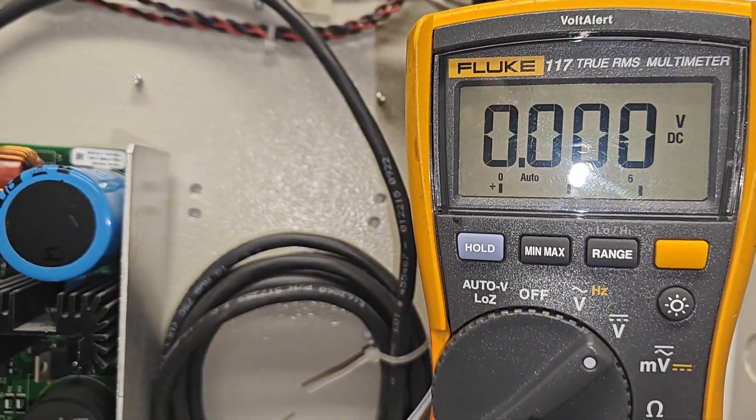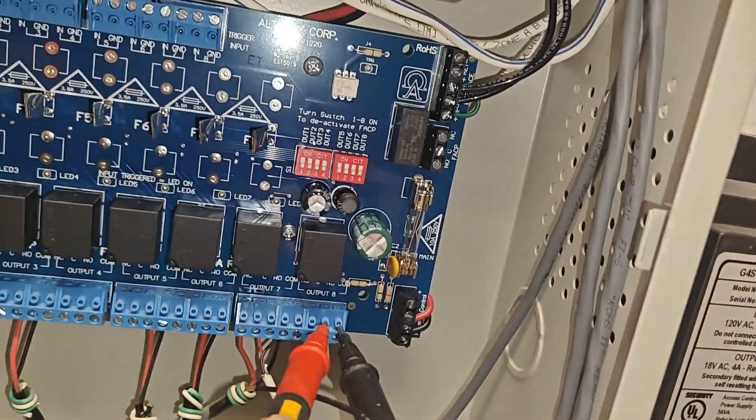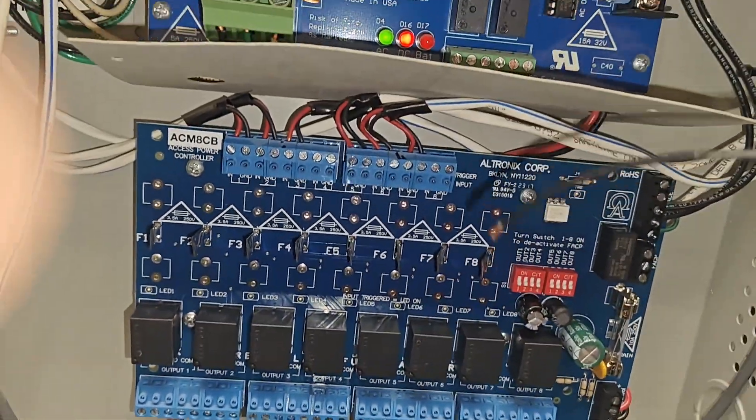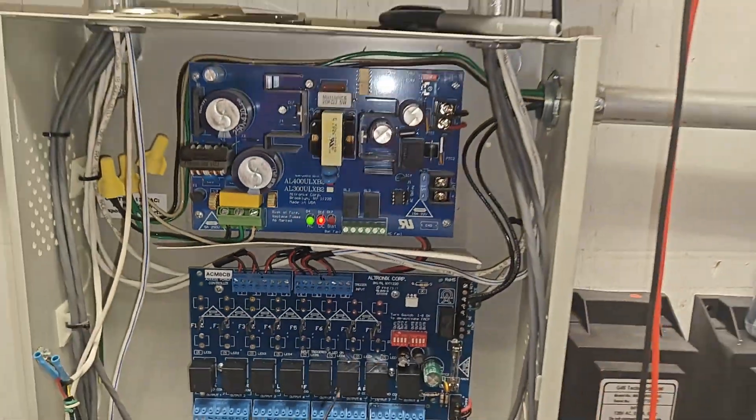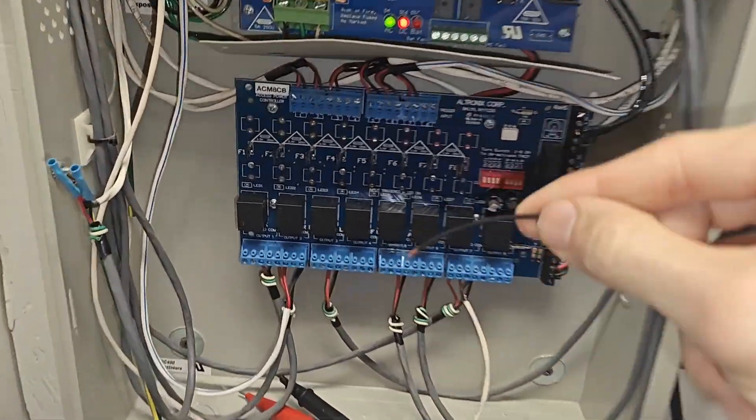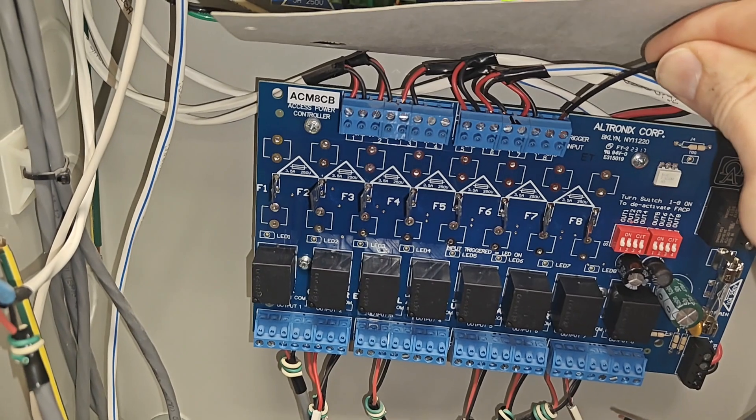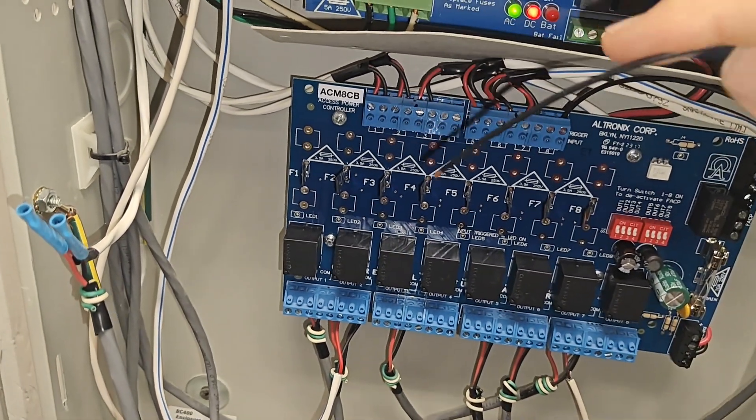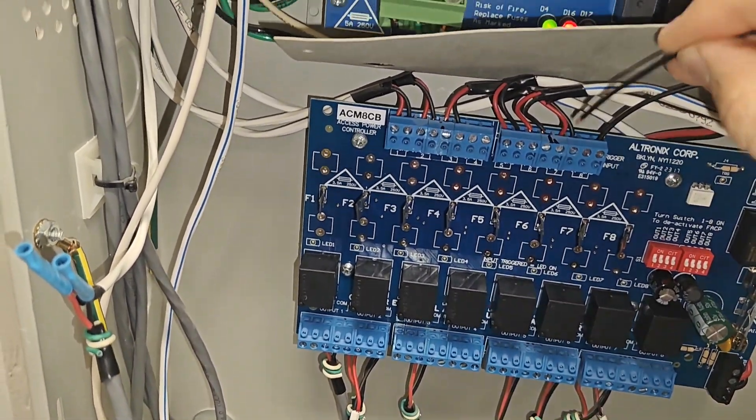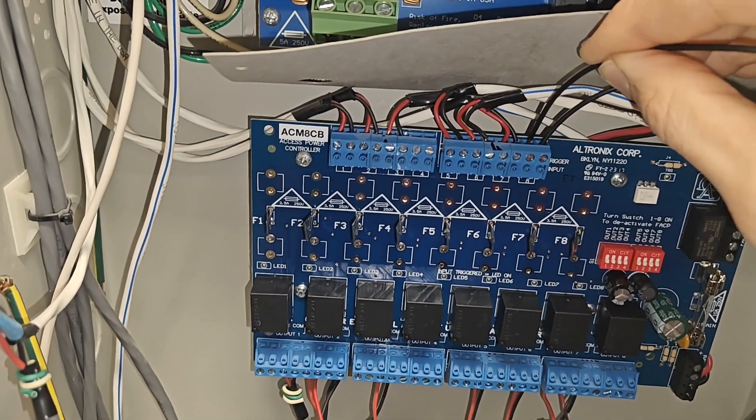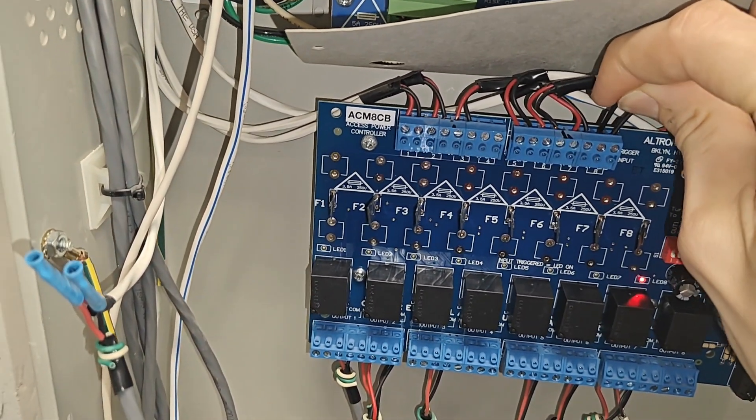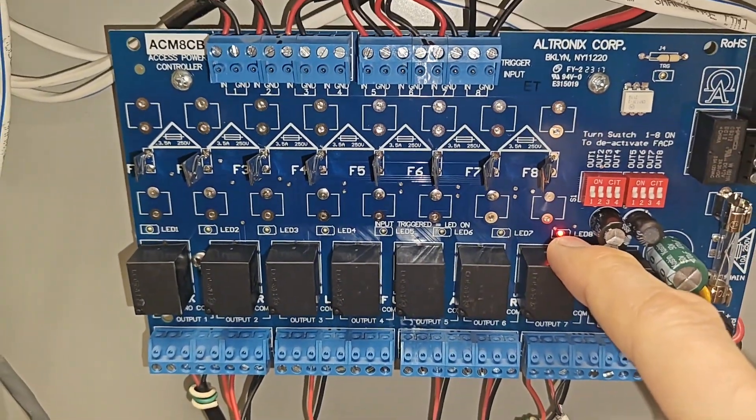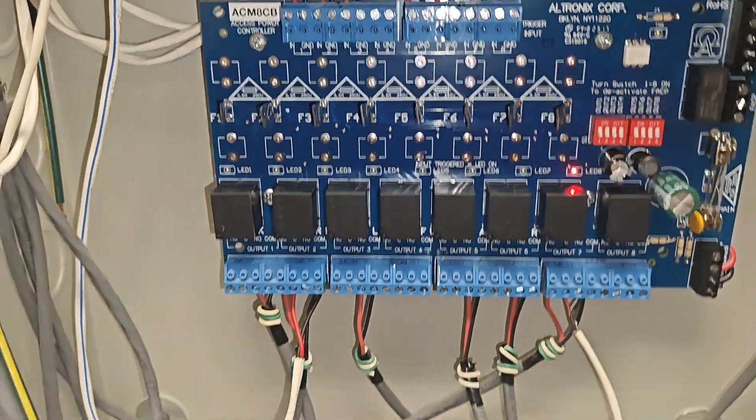So when you put this in here, your voltmeter should be zero. And if you just keep your voltmeter there, and while your meter is there, all you have to do is make a little jumper and you're gonna stick it into the first slot here, and then you're shorting it. There you go, so you can actually see that the relay is lit up.